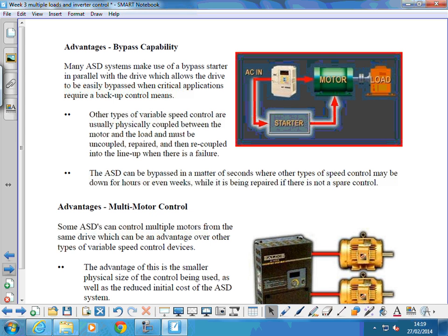Bypass capability. Many ASD systems make use of a bypass starter in parallel with the drive. It allows the drive to be easily bypassed when critical applications require backup control means. So emergency starting of a system under emergency conditions, you have a starter in parallel that just winds the pump up full speed if necessary. Okay. Other types of variable speed would require the motor and load to be physically uncoupled, repaired, and then recoupled to the line when there is a failure. So other systems are less flexible than this in that respect.